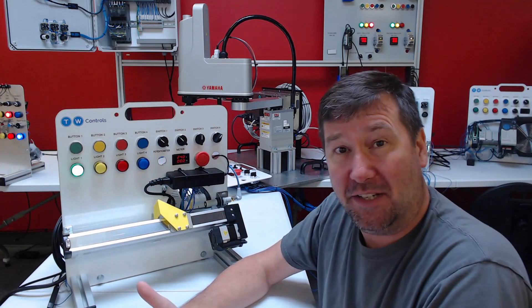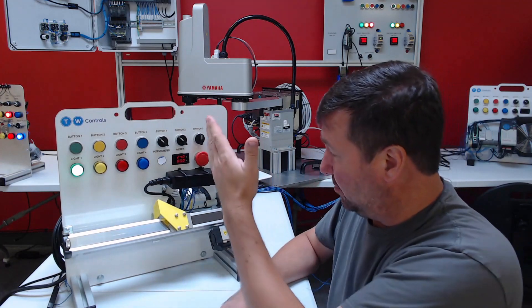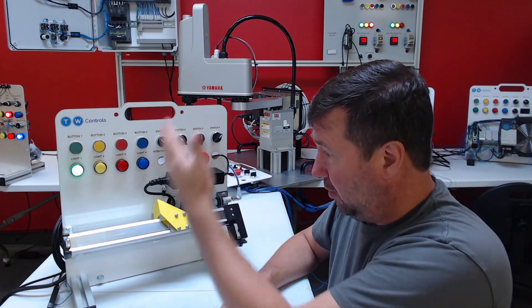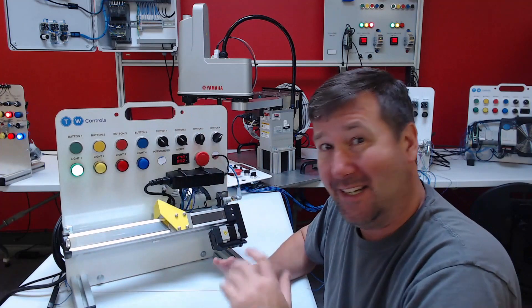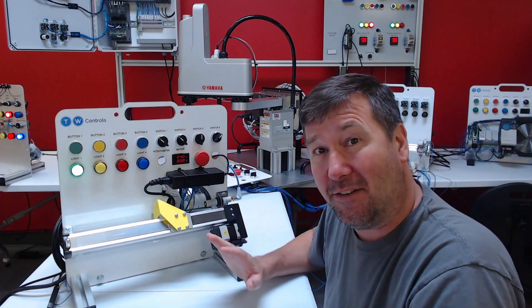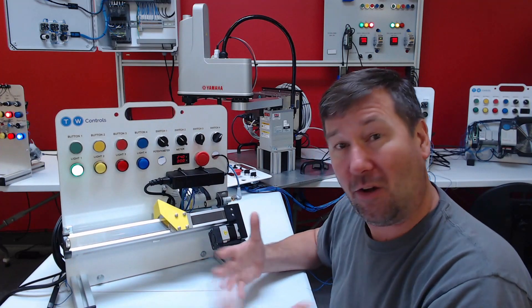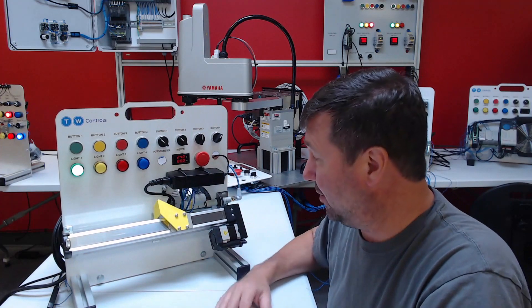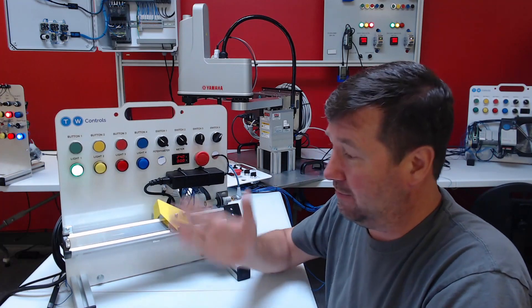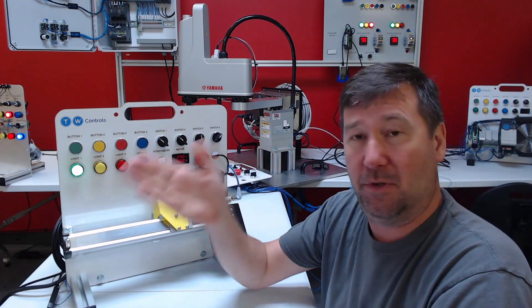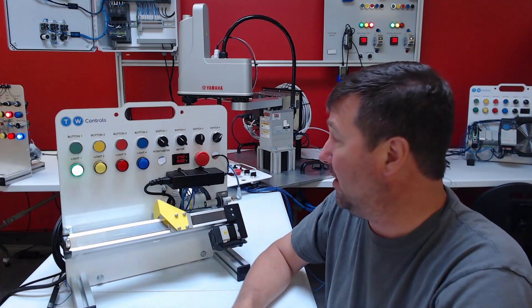So if I didn't want to do the math, or I know I'm always moving from point one to point two to point three, instead of having all that clogging the PLC or clogging my troubleshooting, I can just program those three points on the servo drive and just tell it move point one, point two, point three.